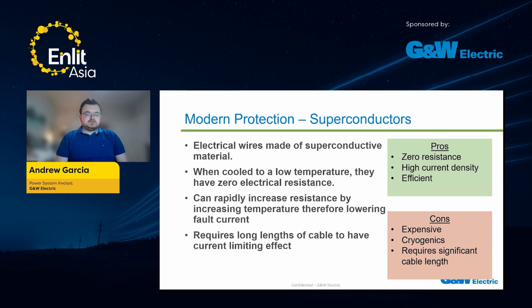So what happens if you increase the temperature? Well, you can rapidly increase the resistance of that wire, therefore adding a lot of impedance to the system, therefore decreasing the amount of available fault current. However, if you think about it, you're going to need a pretty long length of cable to have that desired current limiting effect. You need to add a lot of impedance to your system to do that, but it's something to keep in mind, especially when you are running long lengths of cable, say in designing a transmission system.